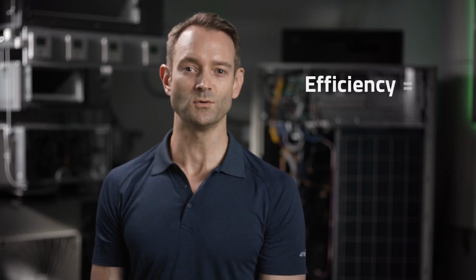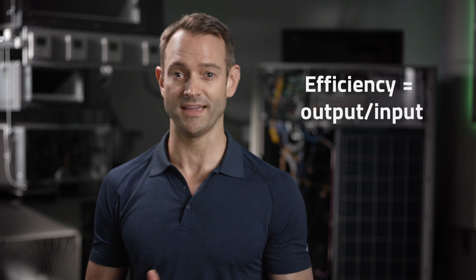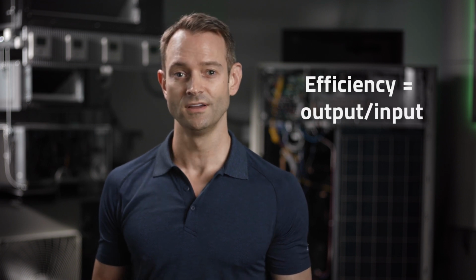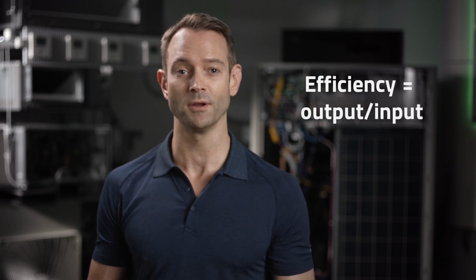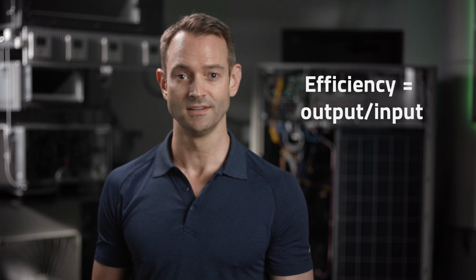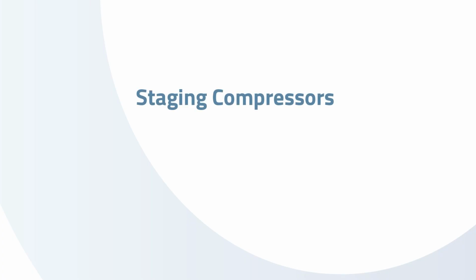Before the development of inverter-rated compressors, load matching was accomplished through several other methods. As we discuss these methods of compressor staging, remember how efficiency is calculated. Efficiency equals output capacity divided by input power. By definition, reducing the capacity with full power input decreases efficiency. These are the methods commonly used for compressor modulation.